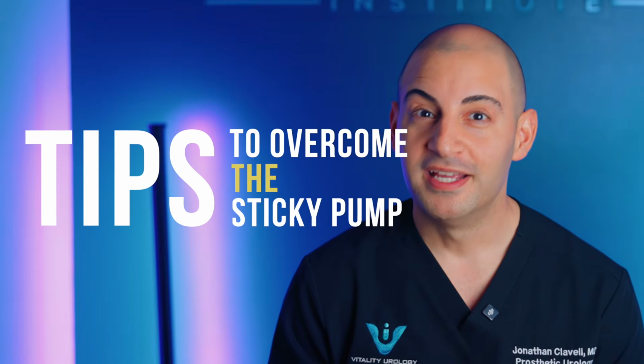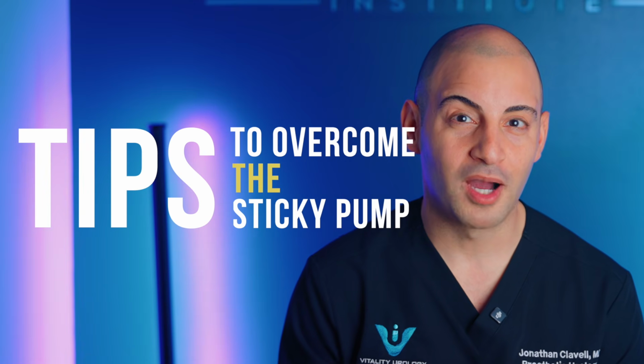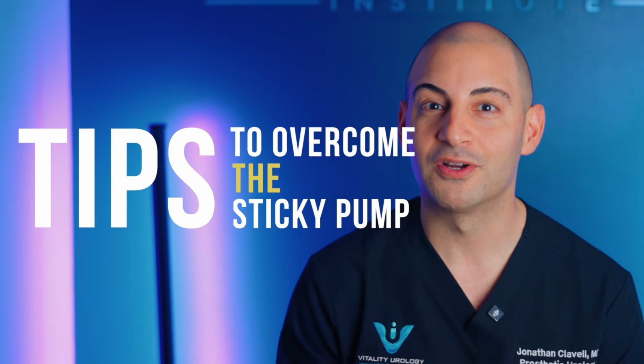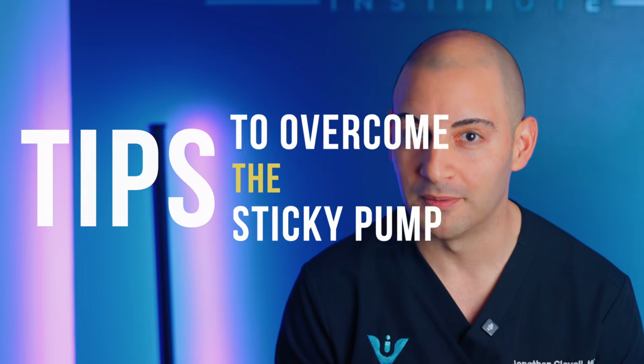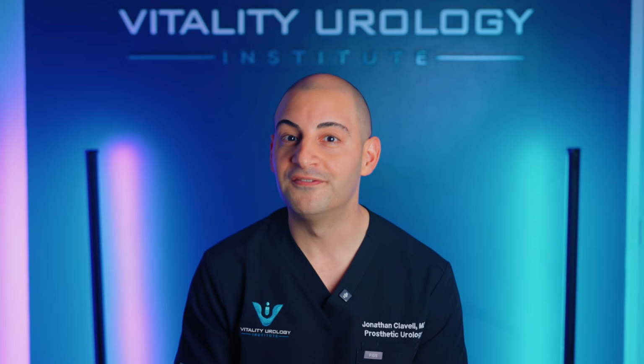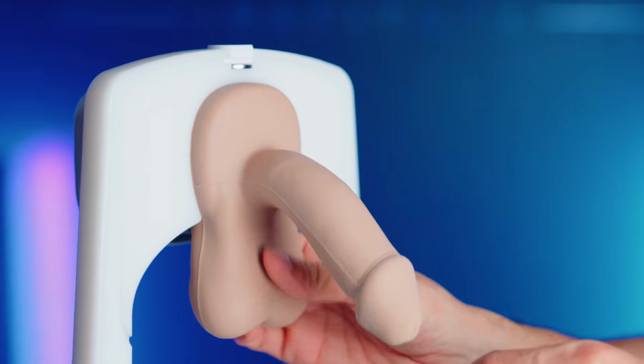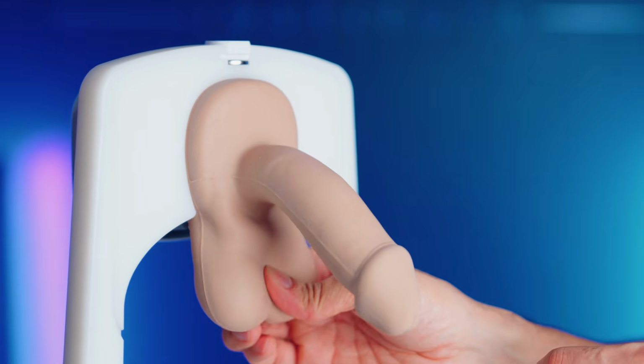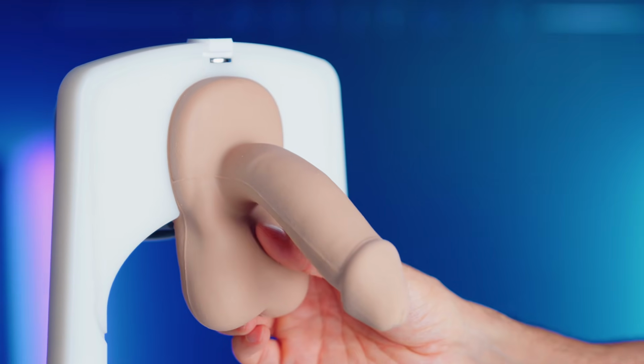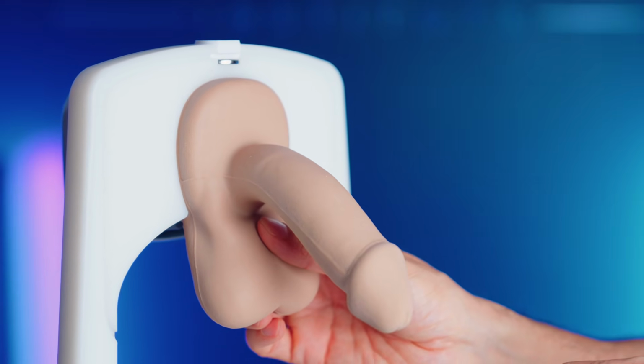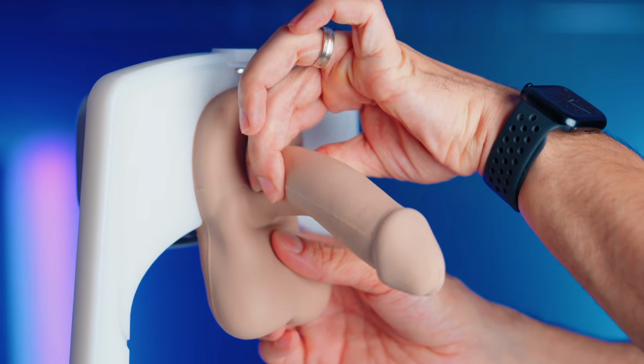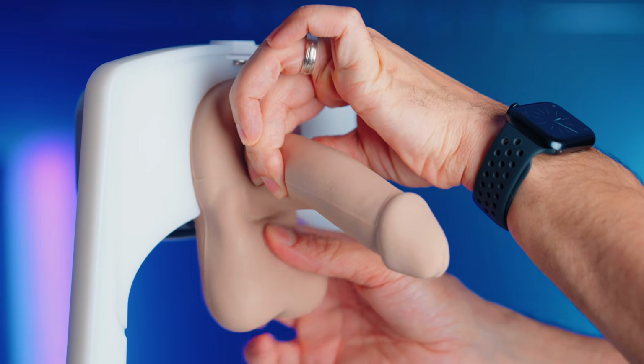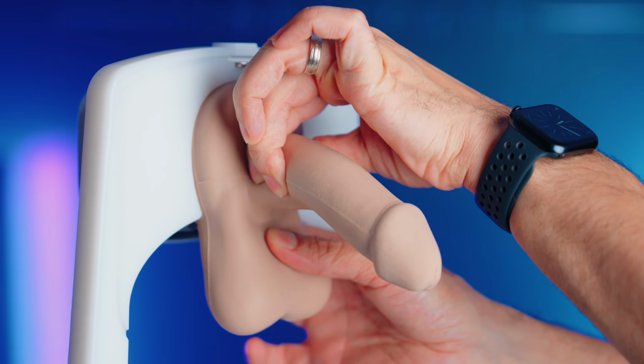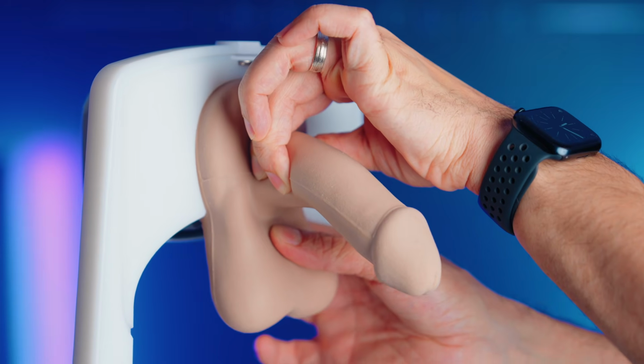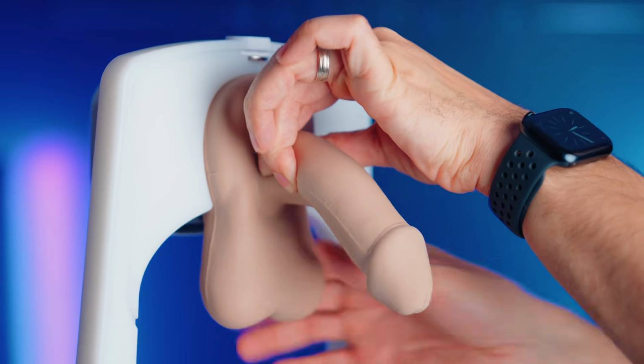On a side note, if you are encountering the sticky pump problem with the AMS 700 MS pump, I have a quick tip that might help you solve the problem. This will require you to try to inflate and deflate the implant multiple times. What I mean by that is that you can start by inflating the penis and giving it a few pumps, let's say 5 pumps, and then try to press and hold the deflate button while you firmly squeeze the base of the penis. Remember, you will know that you are deflating because you will feel the vibration of the pump. That lets you know that you are deflating that implant.